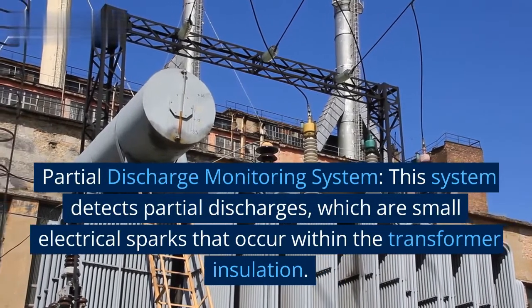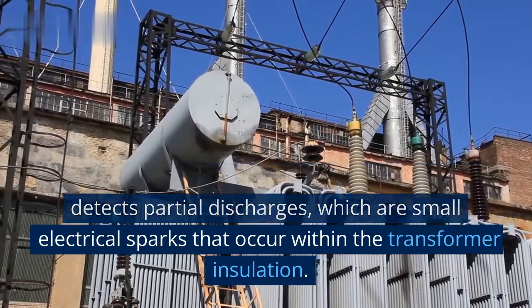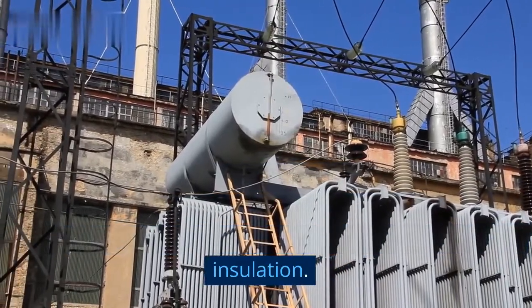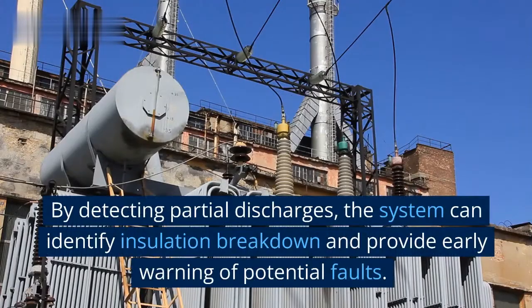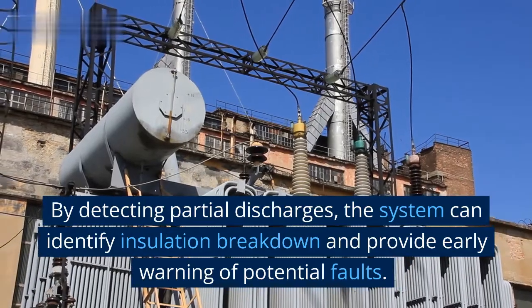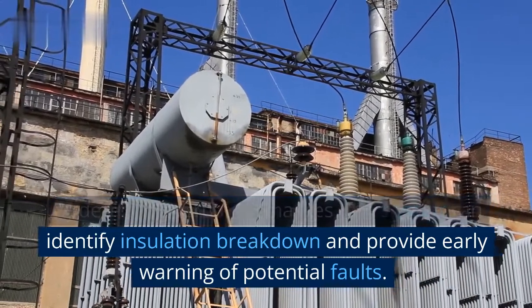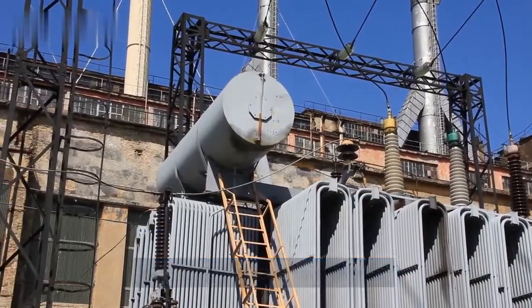Partial discharge monitoring system. This system detects partial discharges, which are small electrical sparks that occur within the transformer insulation. By detecting partial discharges, the system can identify insulation breakdown and provide early warning of potential faults.